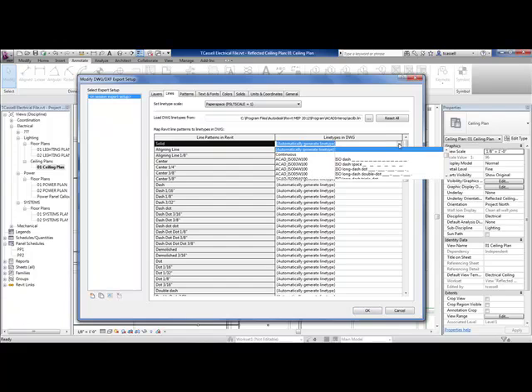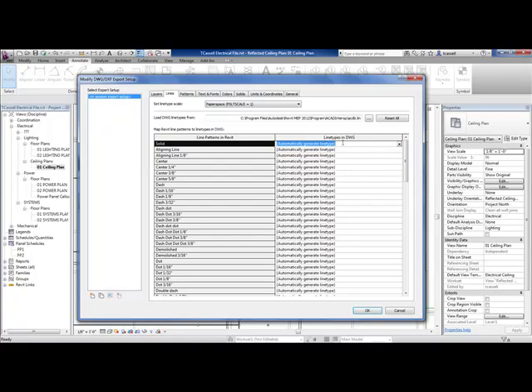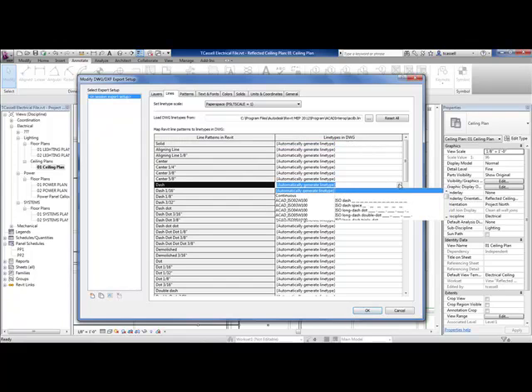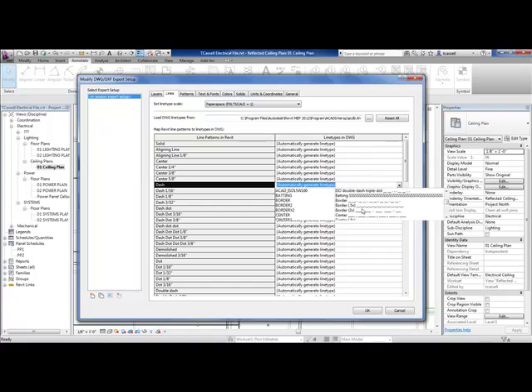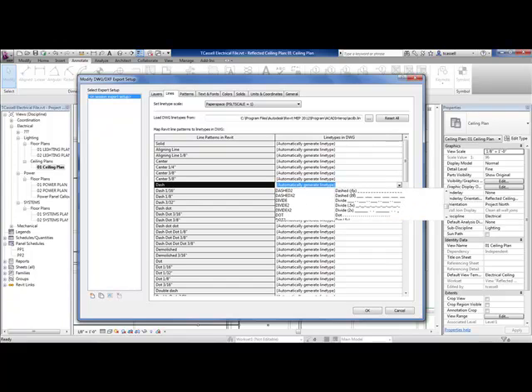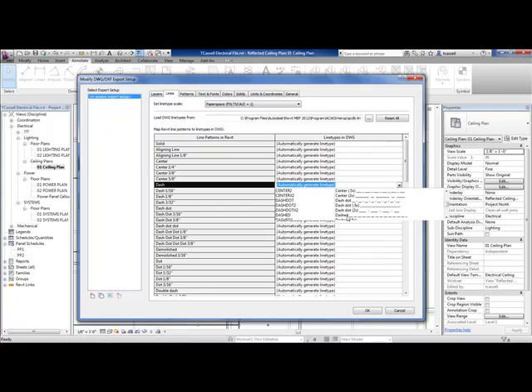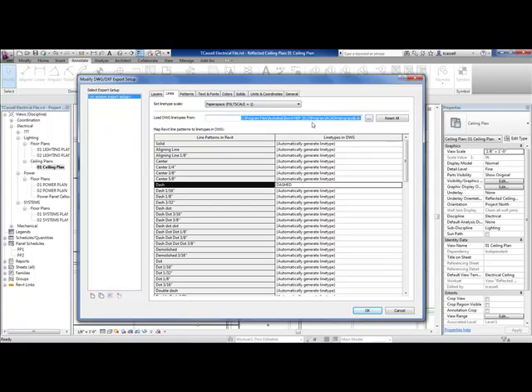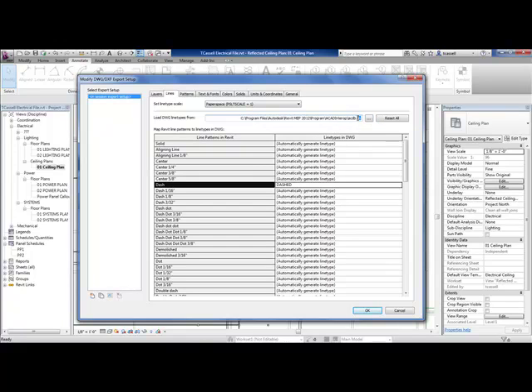When you export to AutoCAD, you can control the line types. You can say what's going to happen now when I export my dashed line type. I can tell it what AutoCAD line type it's going to export to. The dashed in Revit may be equivalent to the dashed in AutoCAD or it may not. As you can see up top, you can load whatever AutoCAD line styles you're using. You can load the LIN file that you're currently using in AutoCAD into here in order to accurately map your export to AutoCAD. It's going to make the export to AutoCAD—the line types and the line weights—come out a lot cleaner.